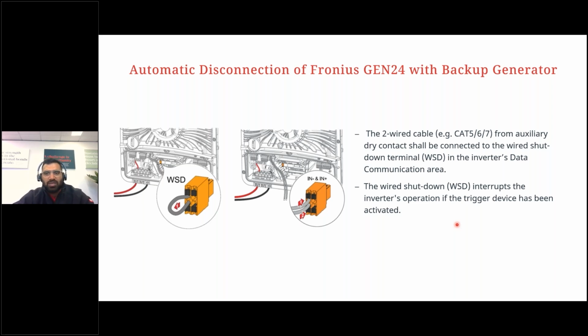All right, so when we talk about backup, we should also look at backup with a genset. You can use the wired shutdown terminal to keep the inverter in standby when the genset is running. In case the customer wants to use backup of the Gen24 and battery combination first before turning on the genset, it is recommended to have a manual changeover switch. This is to prevent the genset from running before the inverter even gets a chance to switch into backup, because we have a 15-second time frame, even with the latest firmware, where the backup from the PV system kicks in. So you can again run a WSD even with this genset and full backup, so that we can put the inverter into standby when the genset is running.